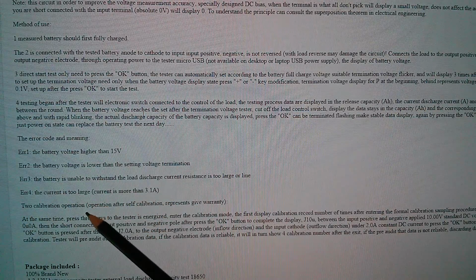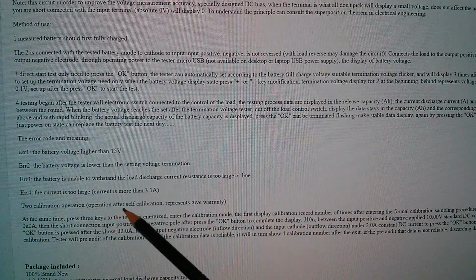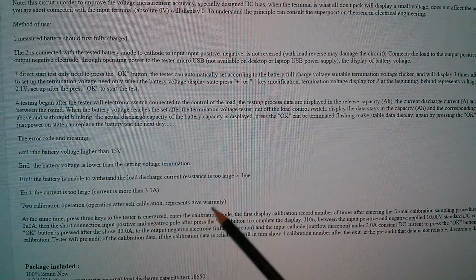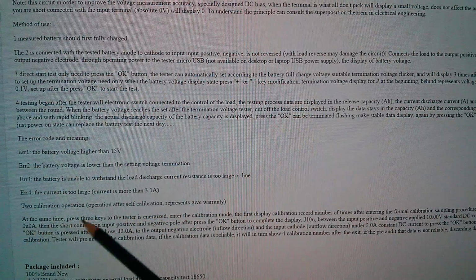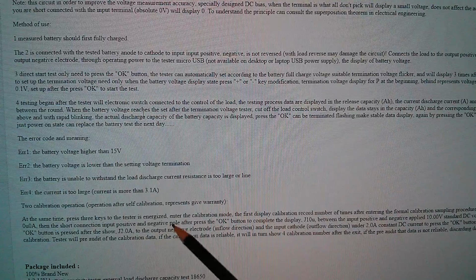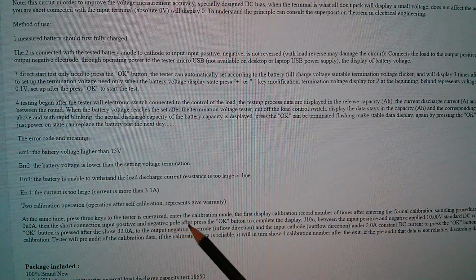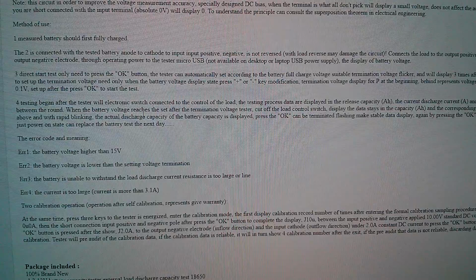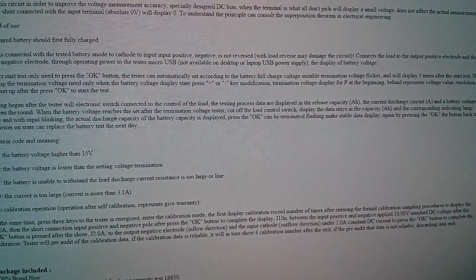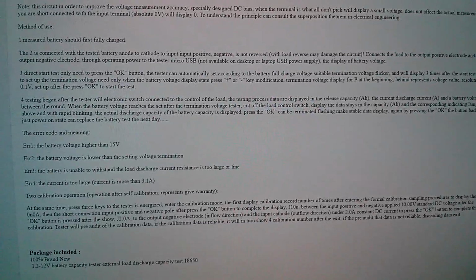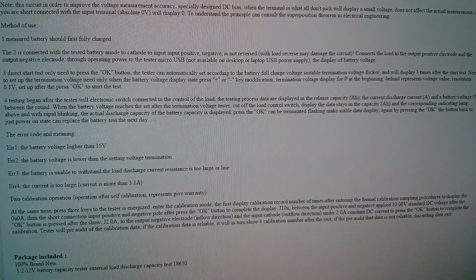Calibration operation. Operation after self-calibration voids the warranty. At the same time, press 3 keys till the tester is energized. So press and hold all 3 keys, presumably, to enter the calibration mode. Oh, all that stuff. I'll just move the camera out and across, so anyone who wants to read all that can.